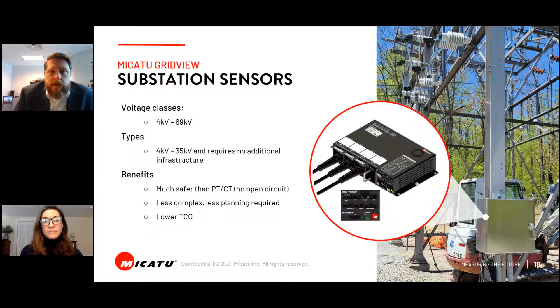The exciting thing about the fourth bay is we've had a really successful partnership with Hubbell, and where I see this technology going is that fourth bay can now actually control different technology. What they did was to actually recloser control, so they can take one of our sensors, plug this device into the fourth bay, wire it up, and now you can control a recloser. Wow, so that's where we're heading, modular, not just sensing but now there's an action. Exactly, that's where we want to go. We want a standardized system for sensing, but also putting in the abilities to do action locally, on the edge, edge processing. That's where we're really heading.